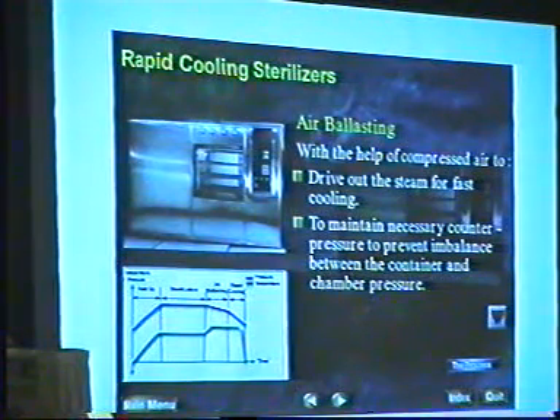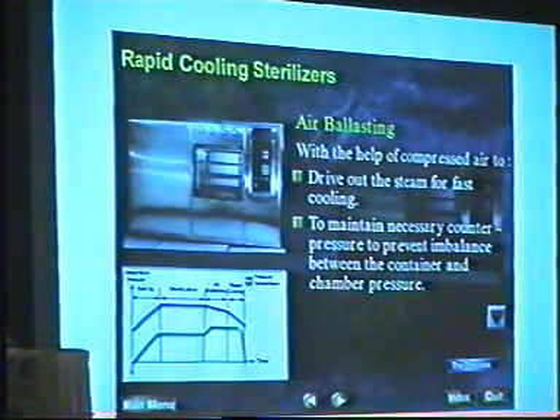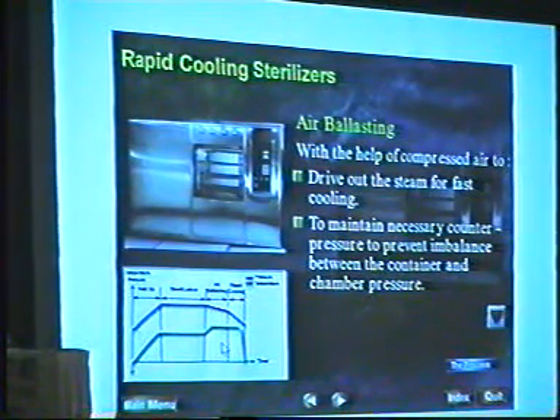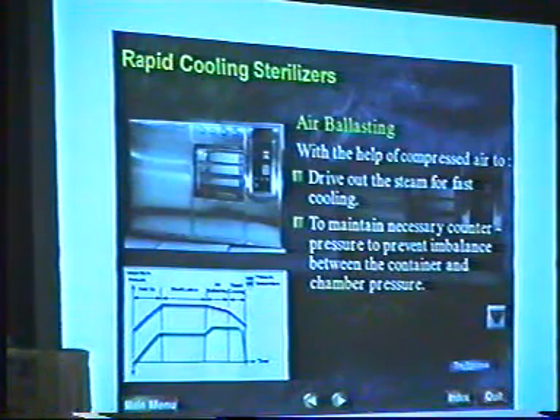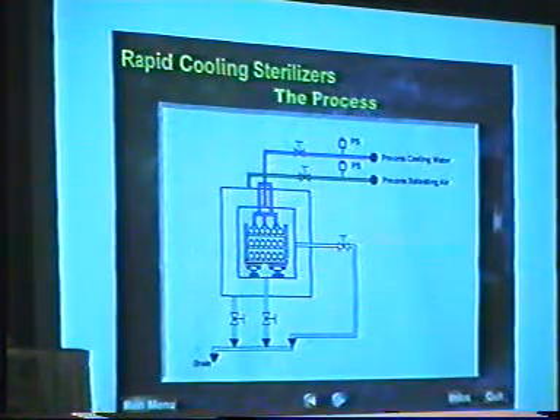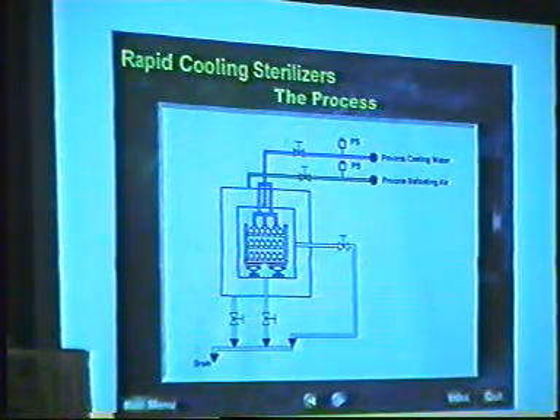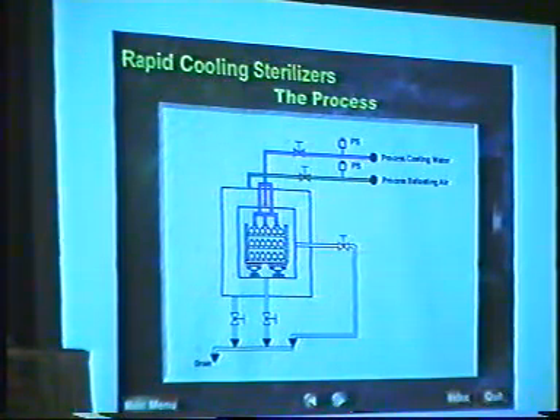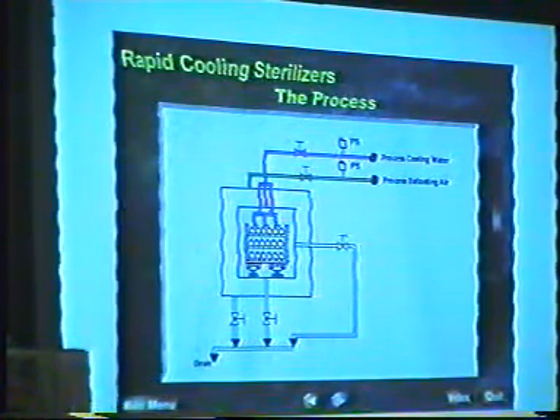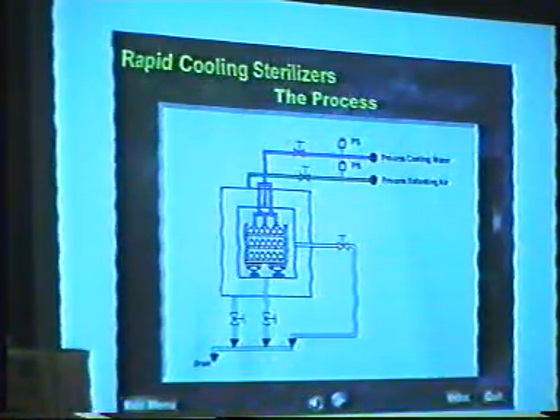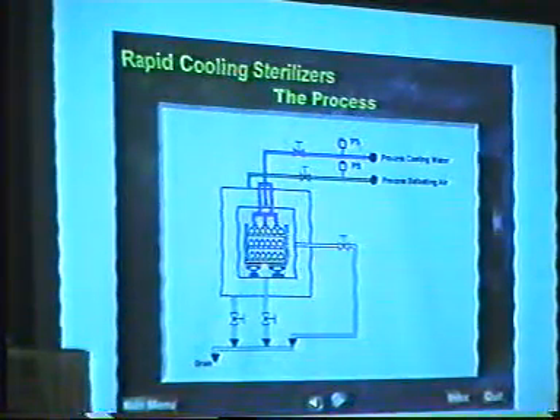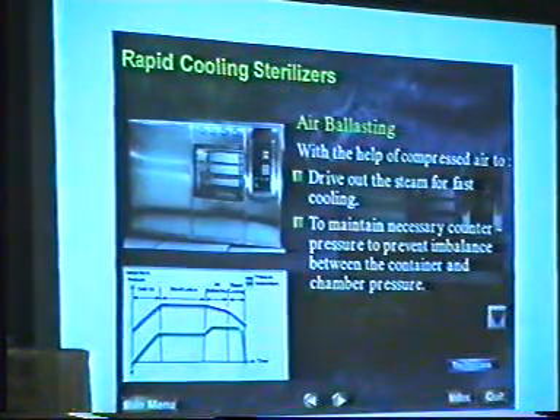At the end of the hold on period, firstly air ballasting is resorted to. Air ballasting achieves two functions. One is it allows steam from the chamber, which was present during the hold on period, to go out. Secondly, it helps in maintaining pressure from outside so that the closure integrity is not questioned.